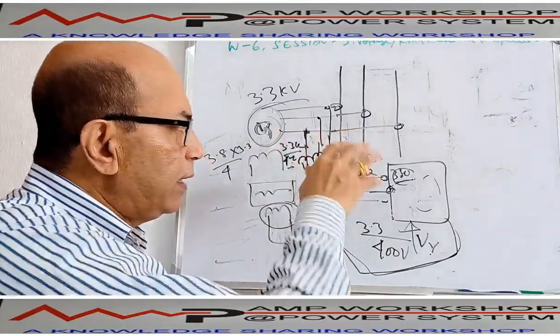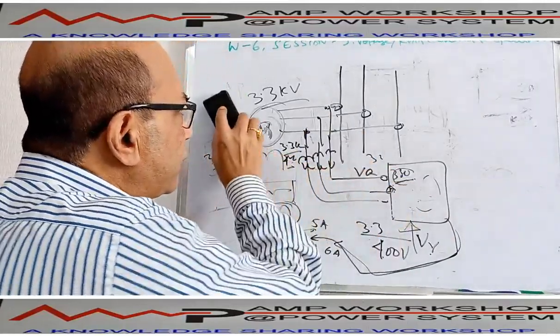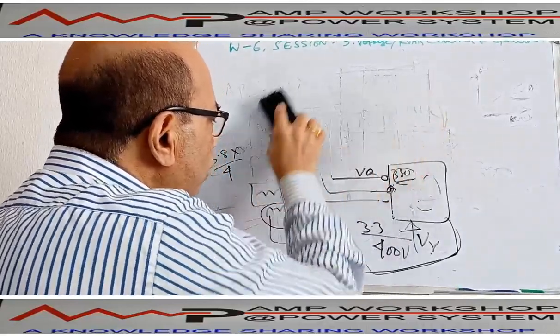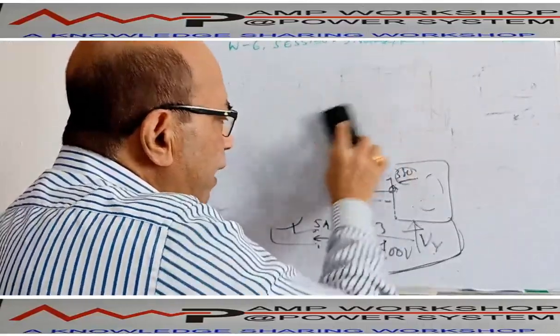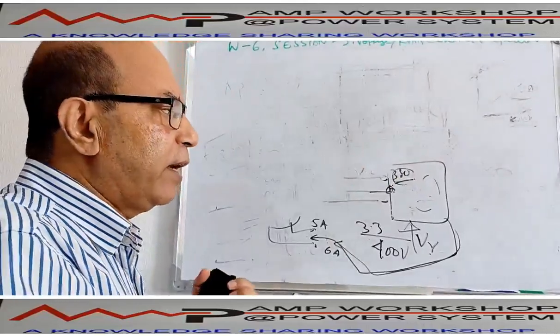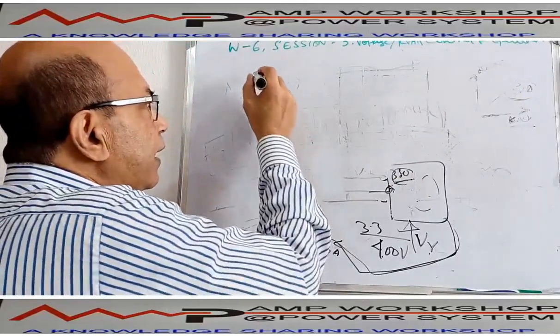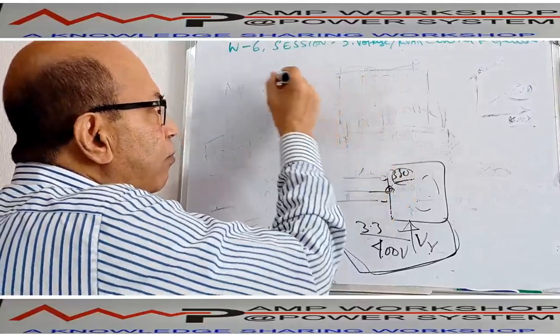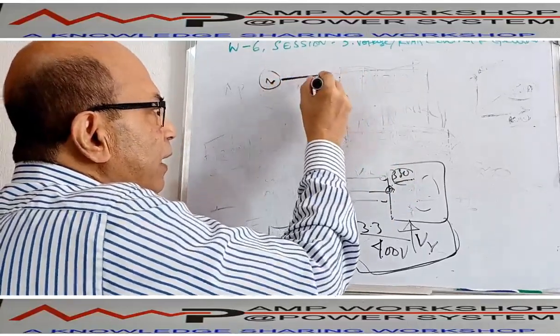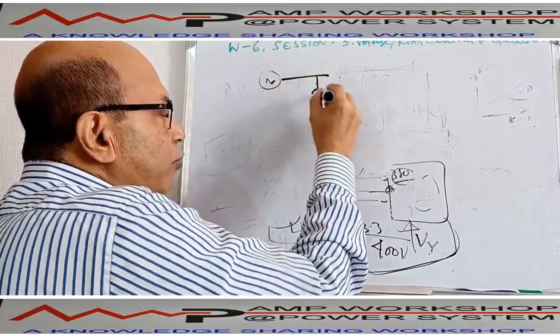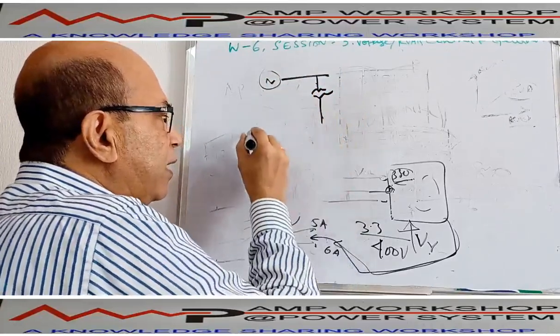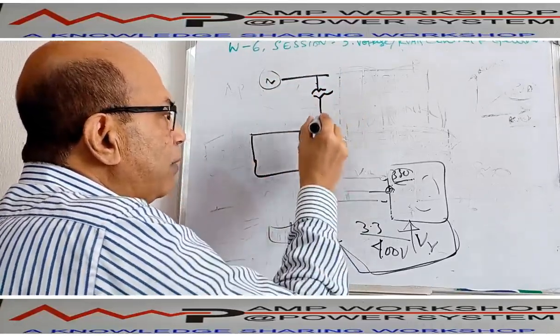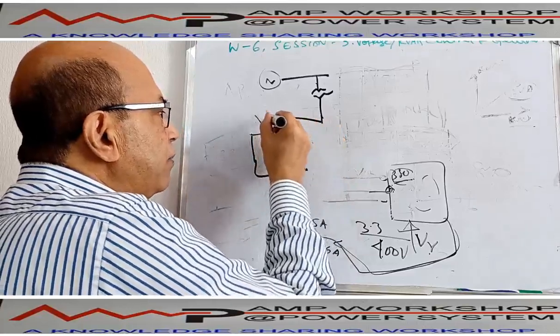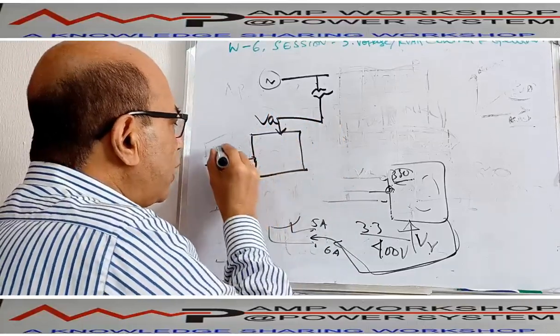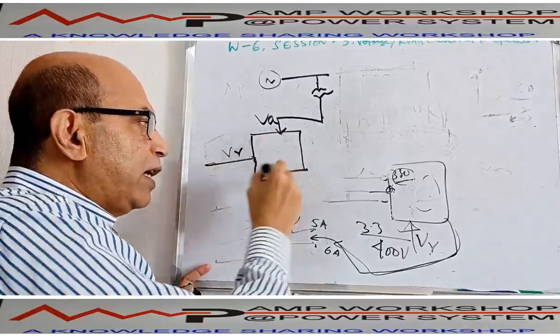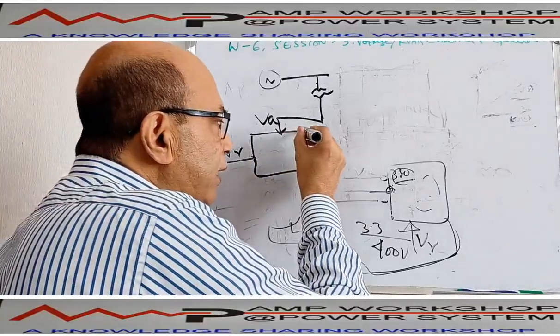So that means in the case of controlling this voltage, same like a speed controller, we have an input device. What is that input device taking? It is taking the PT supply or the terminal voltage from the generator. This is a generator, I am drawing a single line, and it is taking the PT supply to the input device. The PT supply is coming over here, that is V actual, and there is a reference voltage already there, VR. So with that it will compare, then it will create an error signal.